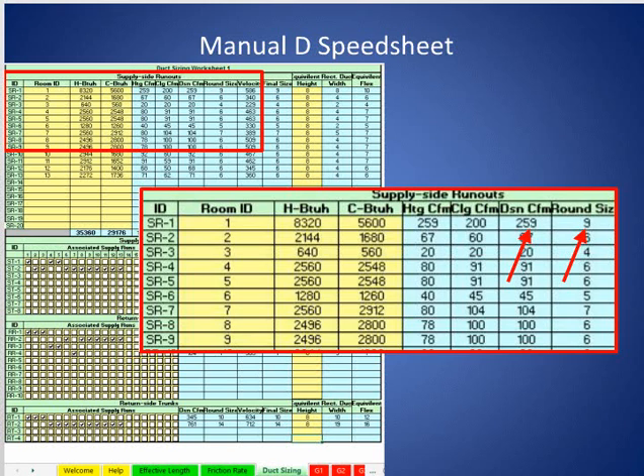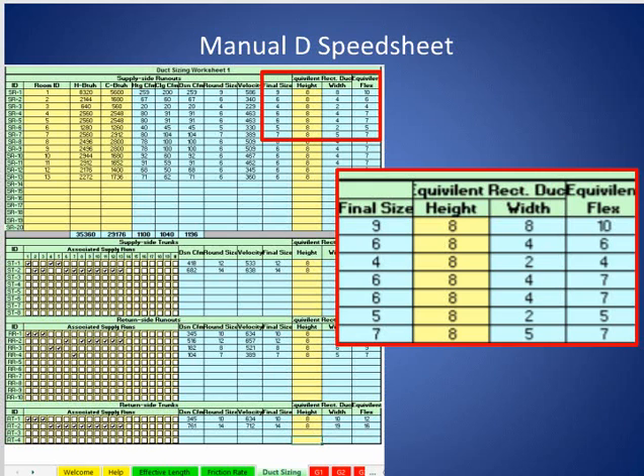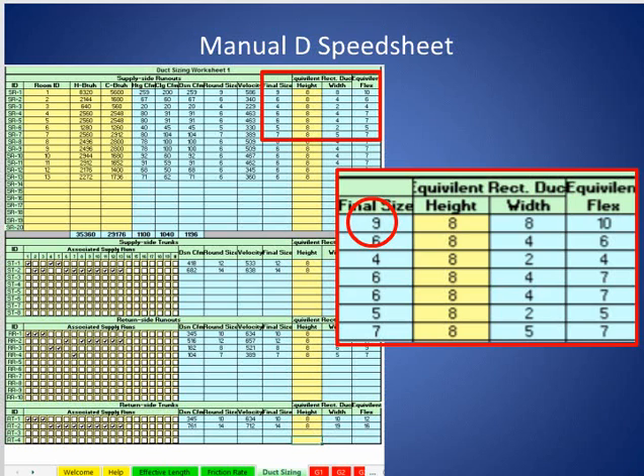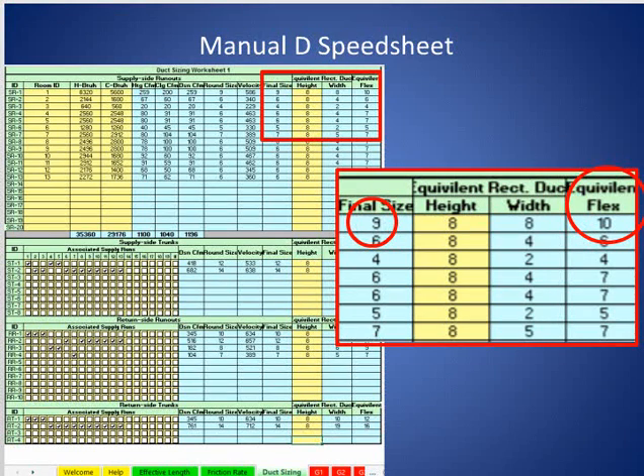In this case we want a 9-inch round duct. Looking at the other corner of the speed sheet across the whole row, we have a galvanized duct final size of 9-inch round. Sometimes you want to run rectangular duct — for example, if you want something narrower than 9 inches in the ceiling. If we put 8 inches in the height field, it automatically does the math: 8 by 8 is equivalent to 9-inch round. We also conveniently have an equivalent length for flex of 10 inches — different from galvanized because there's a different resistance. All the friction chart mathematics is buried in this program and it does the conversions automatically based on your inputs, which is why it's so important to put the right inputs in.